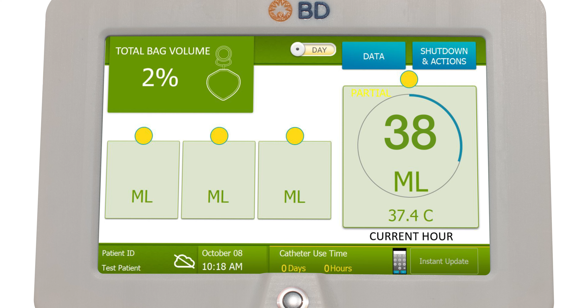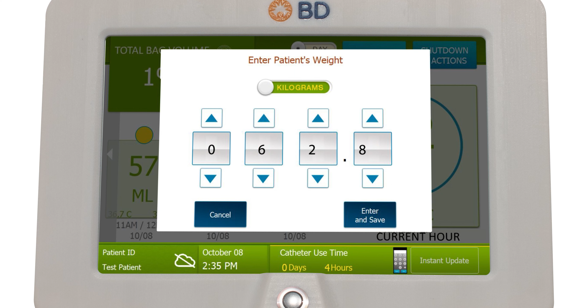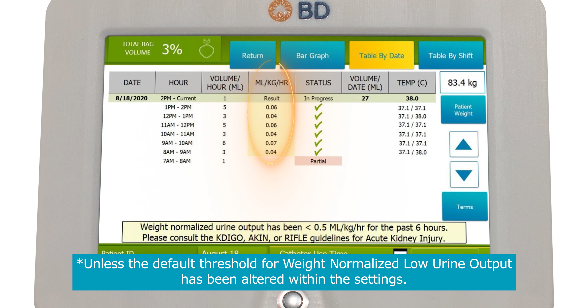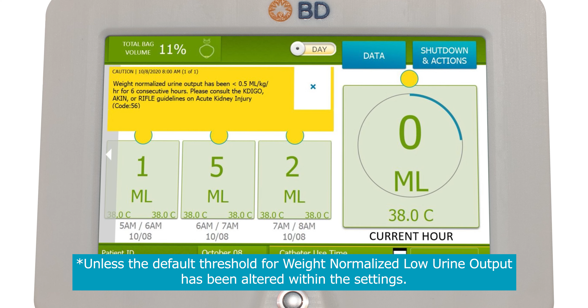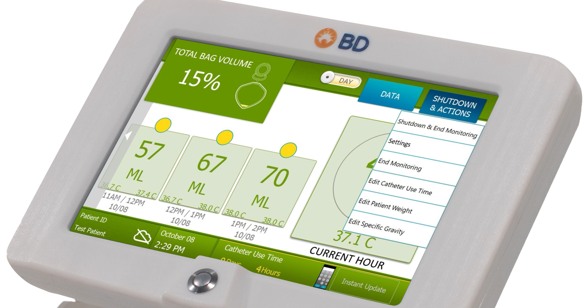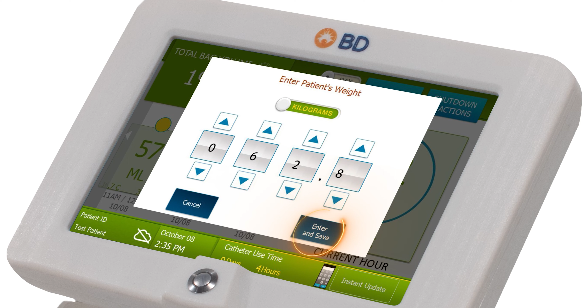Entering the patient's weight when beginning a monitoring session enables the Sensica urine output system to automatically calculate the weight-normalized urine output data. Any value that falls below 0.5 milliliters per kilogram per hour will be highlighted yellow. The system also has a clinical decision support tool with default weight-normalized urine output alarms that align with internationally recognized acute kidney injury identification guidelines. To enter the patient's weight, simply touch the Shutdown and Actions button and select Edit Patient Weight. Use the arrows to enter the weight in and press Enter and Save. Then confirm to return to the monitoring screen.